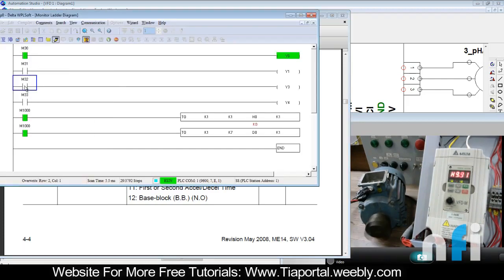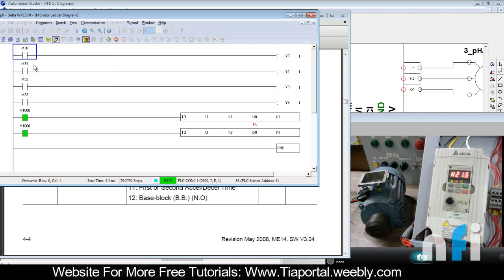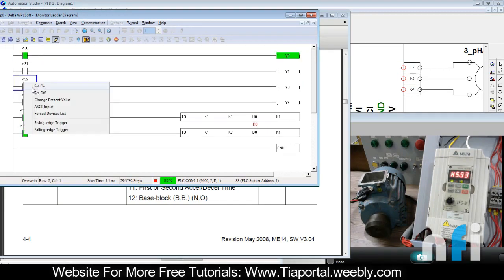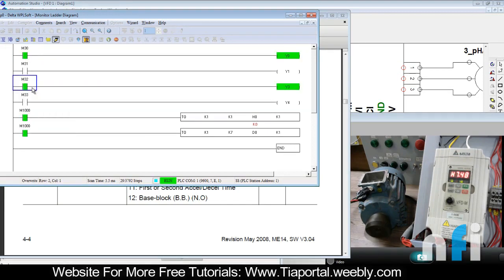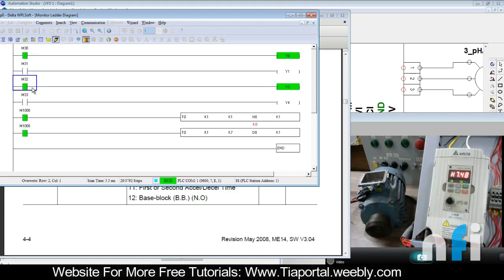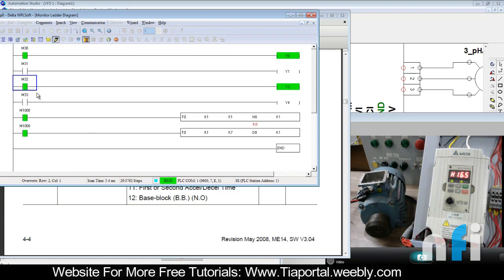This will pause the acceleration. If I set Y0 on without Y3, nothing will happen - it will run smoothly. When I reset, it comes back to 0. Now in the second case, when I turn on Y0 and Y3, it will pause the frequency. The frequency is now paused at 7 Hz. If I release it, it will go back to command frequency. If I set it again, it will pause again.